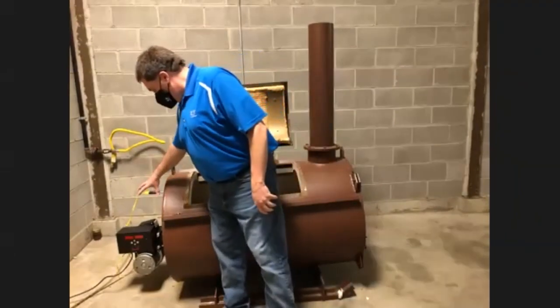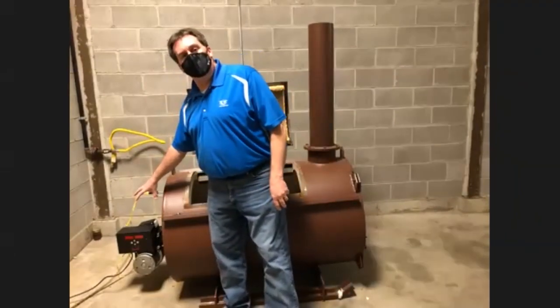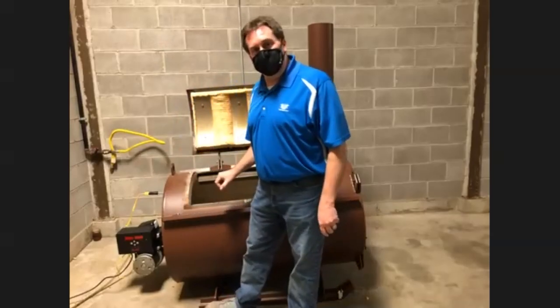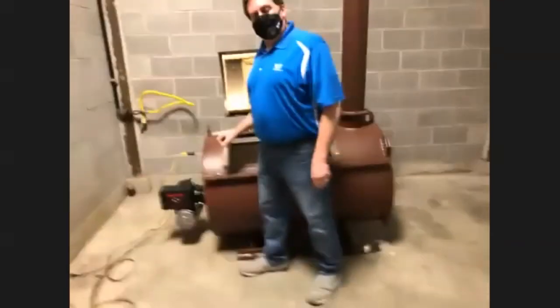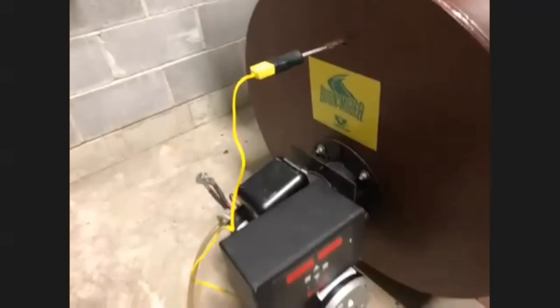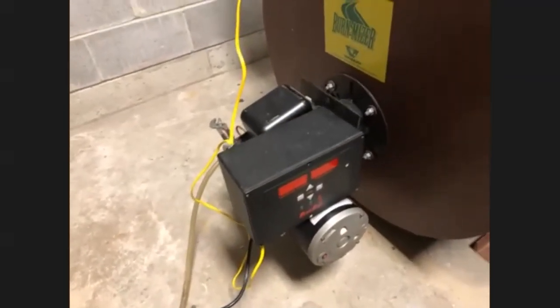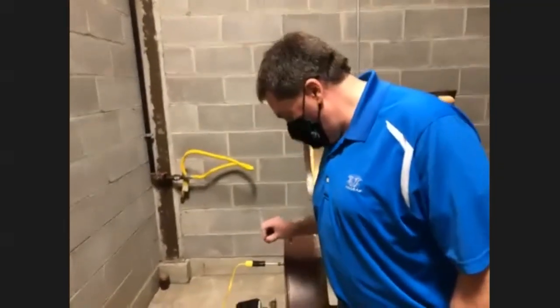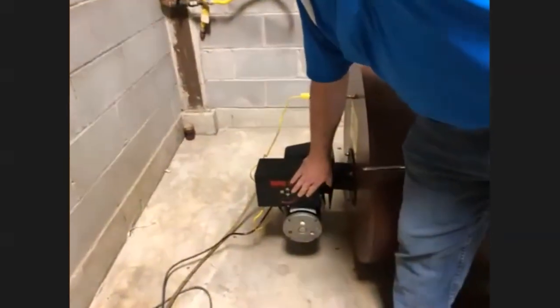Mike has installed an oil burner on here now. He's removed that gas burner, and we put an oil burner on. As you can see here, we have it set up. We've got the temp probe still in there and everything. We're using the same control box as electronic control. Oil burners are much easier to maintain; there's not as much maintenance with these burners. It's still the same programming: 1 hour for every 100 pounds, plus your 30 minutes.